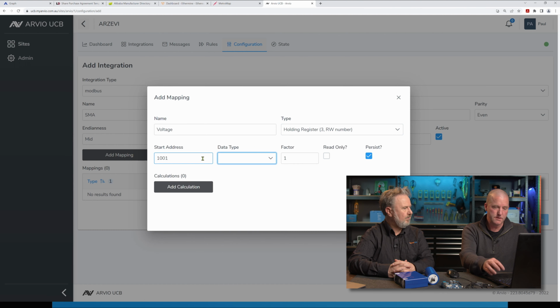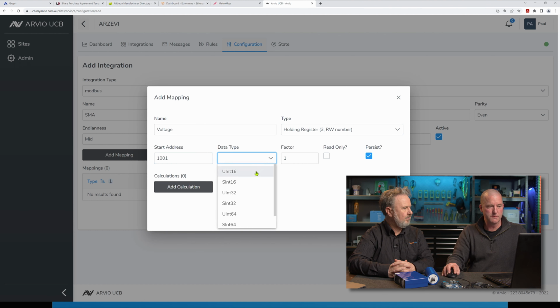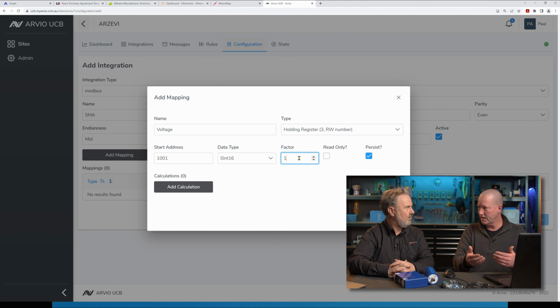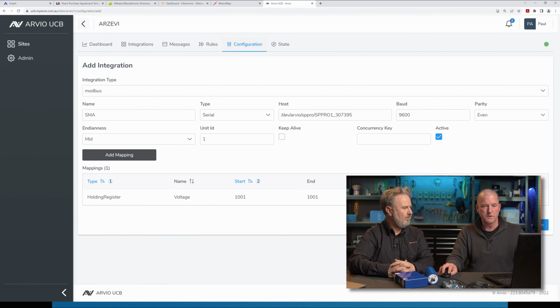Then you give it the start address, which is line 1001 let's say, and the data type, which might be 16-bit - that'll be on the manual too. Whether you want to multiply the number by a factor, so it might be milliamps instead of amps, or volts instead of kilovolts, whatever you want. Add the calculation, press OK, and now that's mapped. I press save, and now I've mapped that device via serial to that inverter on that line number.